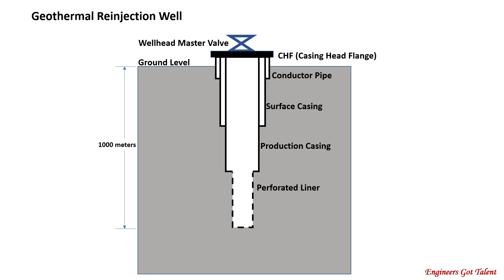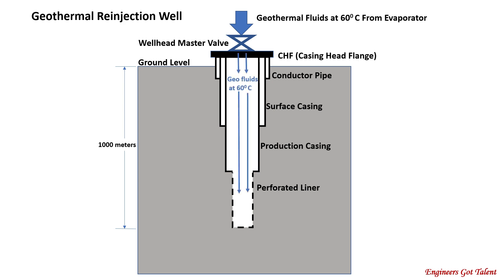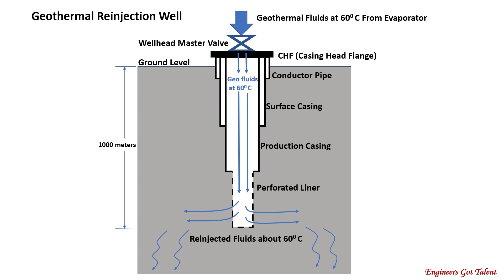To complete the binary process, the warm geothermal water fluid exiting the evaporator is injected back to the substrata at a depth of one thousand meters via a re-injection well. The re-injection well is drilled in an area farther away from the production well and farther away from the geothermal reservoir. The location of the re-injection well must contain permeable rocks to accept the re-injected geothermal water. The re-injection well has the same casing strings configuration as the production well. Strictly, there must be no underground link between the re-injection well and the production well, otherwise the re-injected water will cool down the production well and the geothermal reservoir, thus reducing the production well's output.